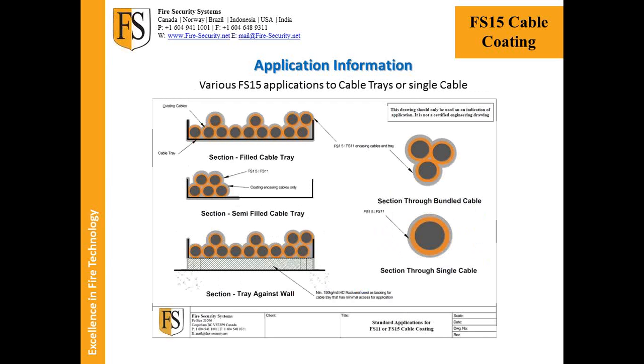So with our applications of FS15, here you will see a typical drawing, which we send out quite regularly, showing how the cable coating is applied. So if we're looking at a single cable, effectively we coat the entire surface of that cable to stop spread of flame. Usually if it's a high voltage cable, this will be sitting on a concrete floor, and you'll come along and spray right down and underneath that. I have seen in some instances that some customers want to tape either side of that cable on the concrete itself, anywhere 2 or 3 centimeters away from the cable, and then they spray that area. It's not overly necessary at all, but they do that to make it look nice.